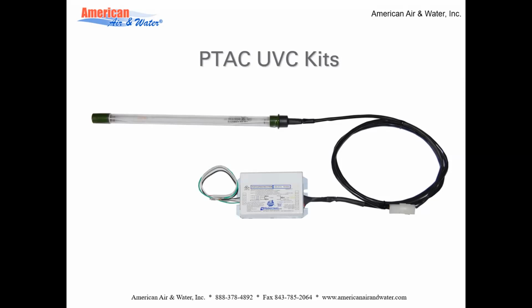One of them from Barry. He wants to know if the UV systems break down things like belts, insulation, vinyl tubing, electrical wires, things like that, and what steps should be taken to protect those materials. In most cases, UV does not penetrate deep enough into materials to inflict structural damage. However, some thin materials may suffer under UV exposure, and this is specifically plastics, which are not UV inhibited. Protection could be they could be spray painted with aluminum paint or covered with aluminum duct tape. This will provide complete protection against the UV.